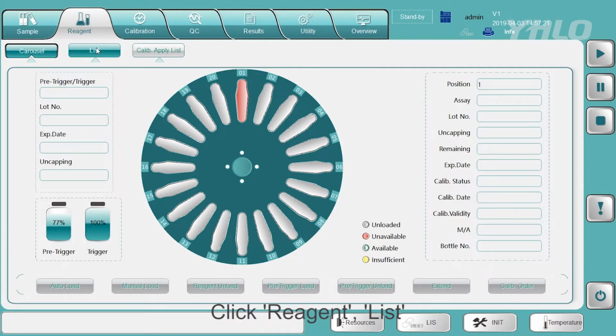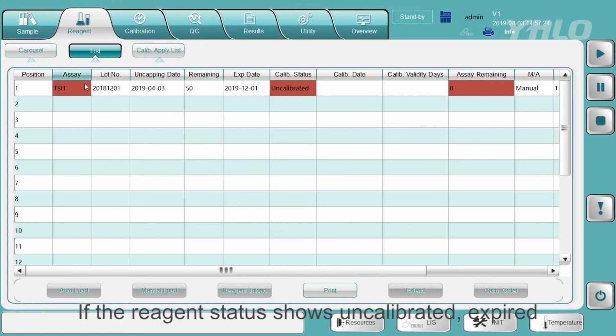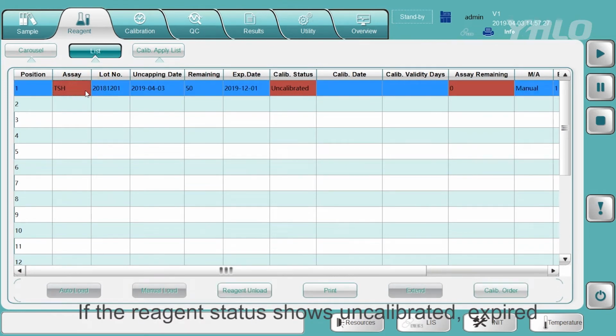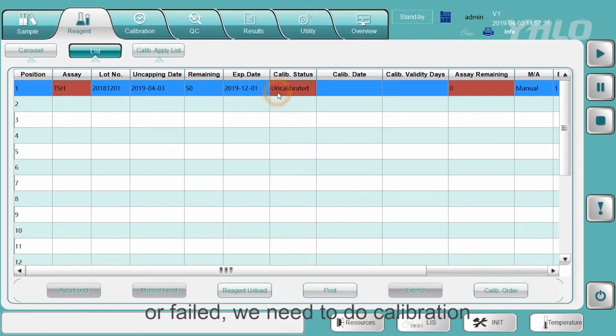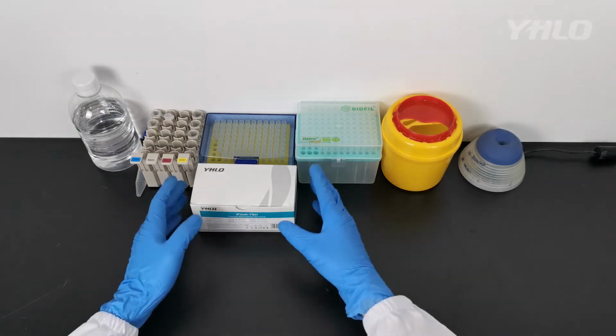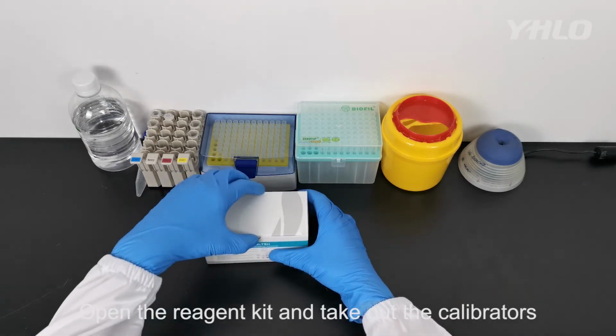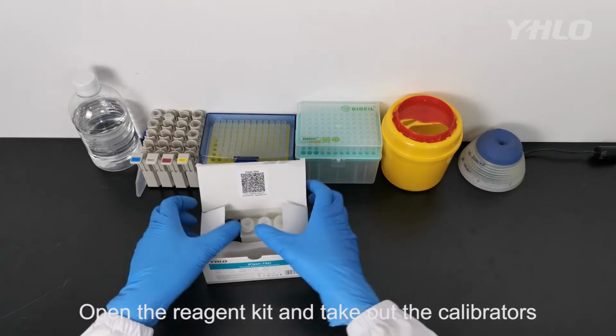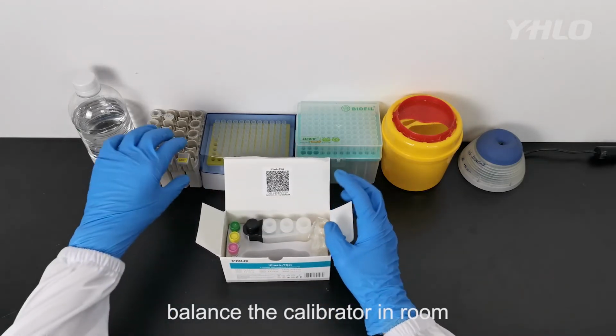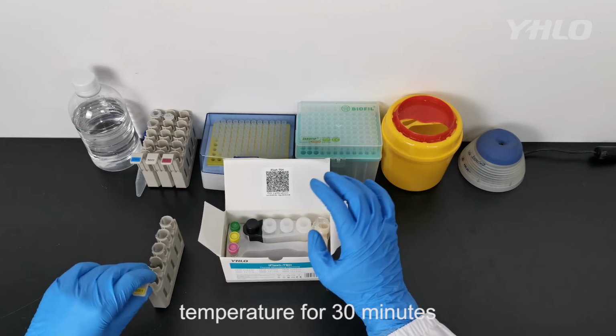Click Reagent List. If the reagent status shows uncalibrated, expired, or failed, we need to do calibration. Open the reagent kit and take out the calibrators. Balance the calibrator in room temperature for 30 minutes.